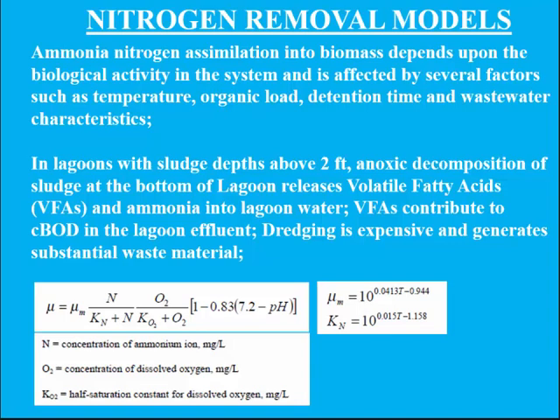In these lagoons today, we are accumulating sludge at the bottom — four or five feet of sludge. That's going to impair lagoon performance. In fact, the sludge will make its own ammonia: when you decompose biomass under anoxic conditions, it makes ammonia. So any lagoon with five feet of sludge is going to be an ammonia producer, and your effluent ammonia will be higher than the influent. The lagoon is not solving anything — it's creating a problem. Dredging is expensive, generates a lot of waste, and is not a good solution.